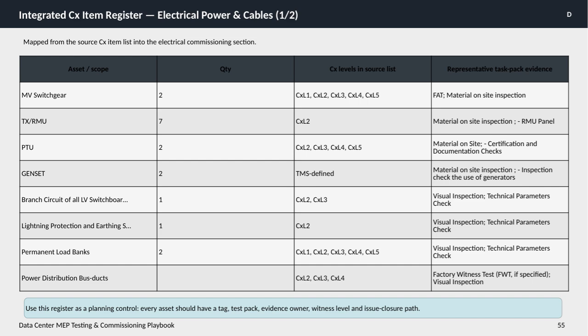Other critical equipment like transformers, PTUs, and gensets also have defined commissioning tasks, including visual inspections and documentation checks to verify certification. Power distribution components, such as bus ducts and switchboards, undergo a combination of visual inspection, technical parameter checks, and factory witness tests where applicable.